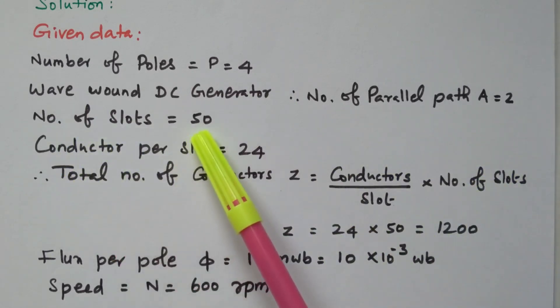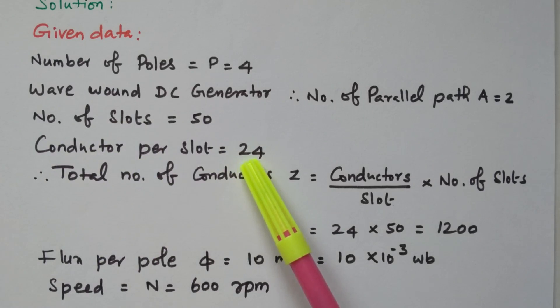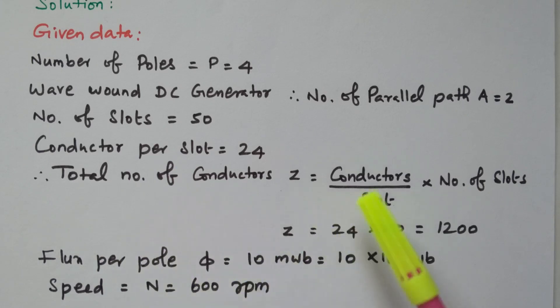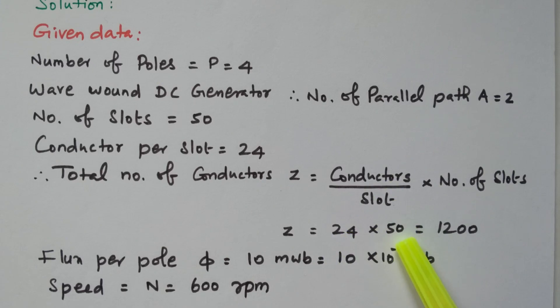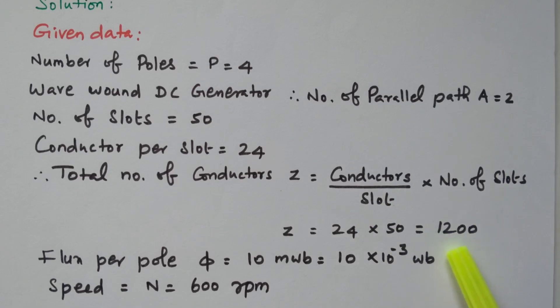The number of slots is 50, and conductors per slot is 24, so 24 conductors are available in each and every slot. The total number of conductors Z equals conductors per slot multiplied by number of slots — that is 24 into 50 — equals 1200. So the number of conductors is 1200, calculated from conductors per slot into number of slots.